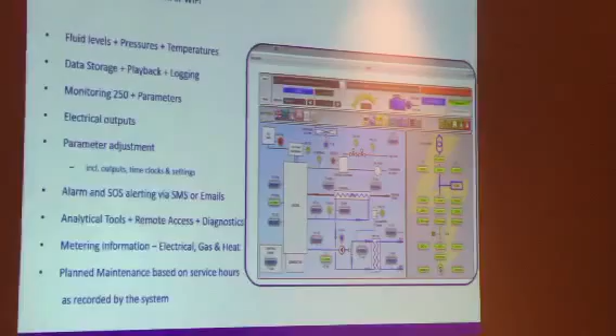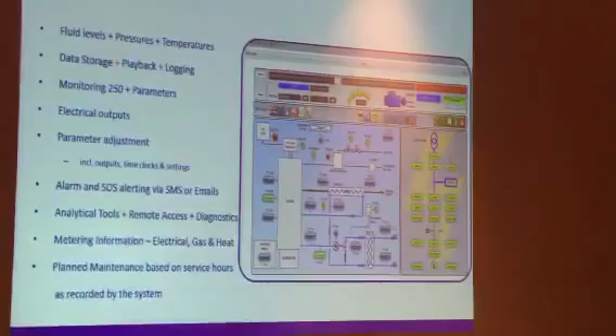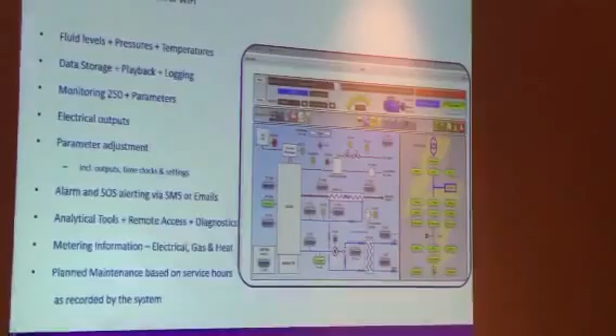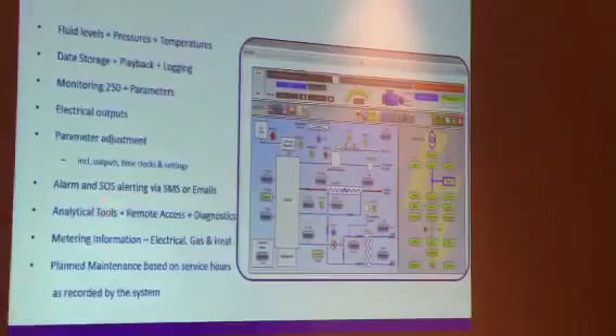We're monitoring approximately 250 plus parameters. We can see live electrical outputs and adjust parameters remotely - this could be reducing the output electrically, or changing set points to enhance performance. The system has alarm and SOS alerts, sent via SMS or email, so if the machine has a problem it can send an automatic email to the required person, whether that's the end user, the engineer, or the control desk in Manchester. It also provides analytical tools, remote access and diagnostics.